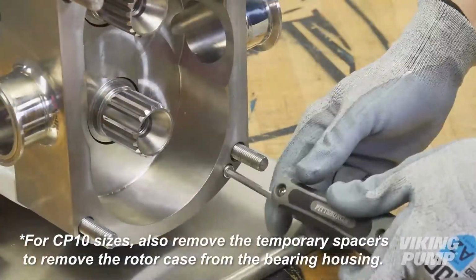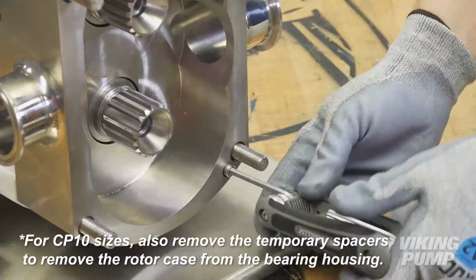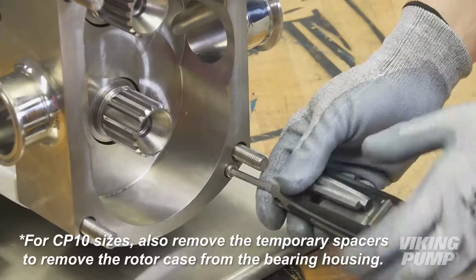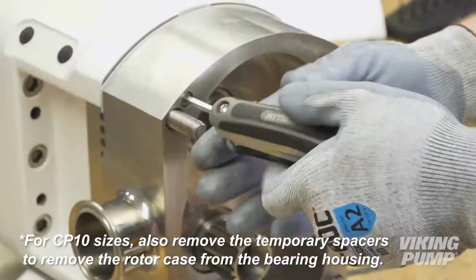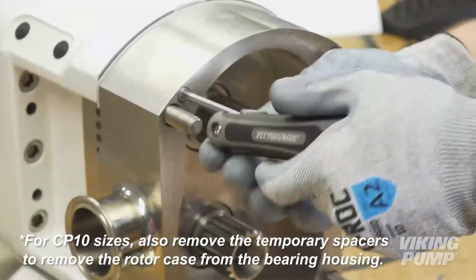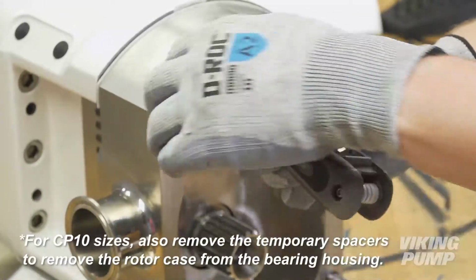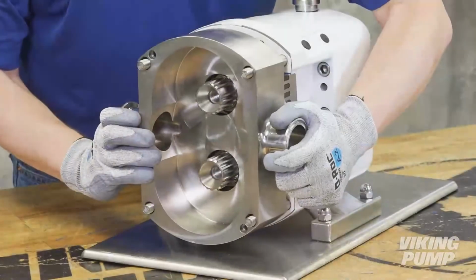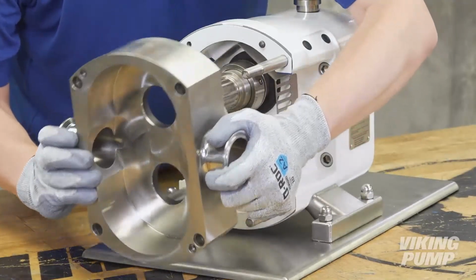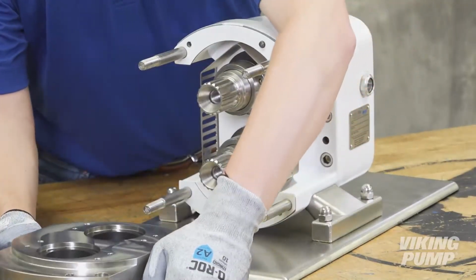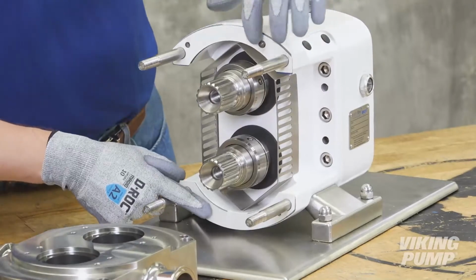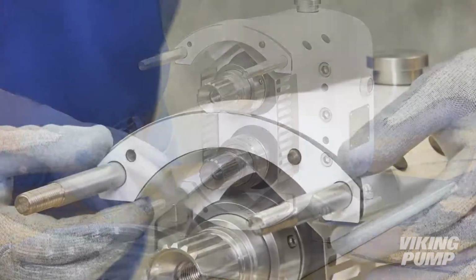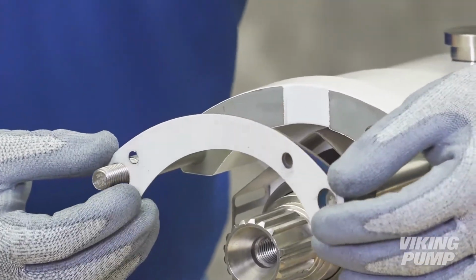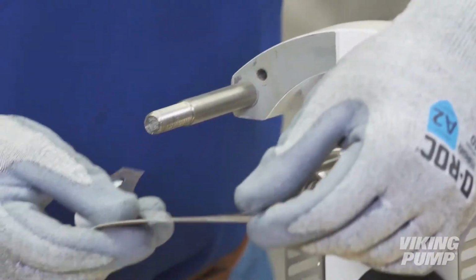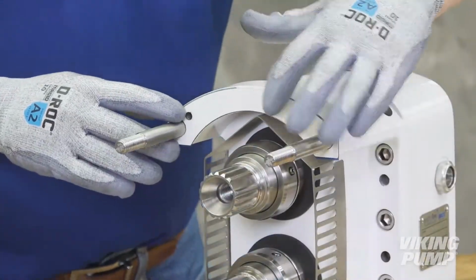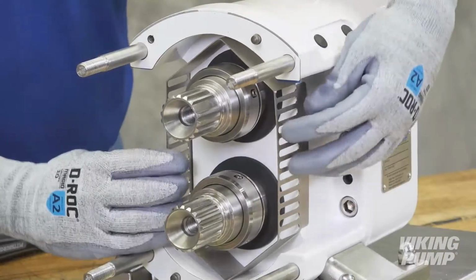For CP20 and CP30 models, remove the socket head cap screws and slide the rotor case from the bearing housing. For CP40 models, remove the dome nuts from the gearbox that retain the rotor case to the gearbox. Dowels locate the pump on the bearing housing, so a soft-headed hammer may be used. Shims may be found behind the casing. Make note of which location each set comes from, as they need to go back to the same location later. Remove the guard.